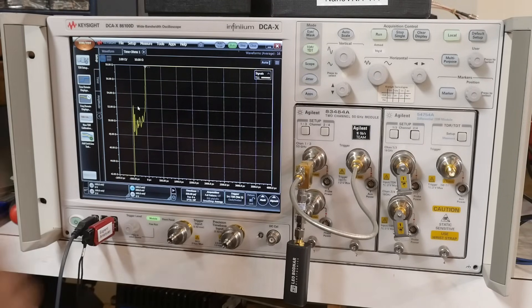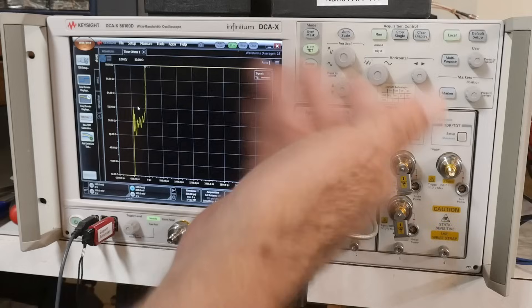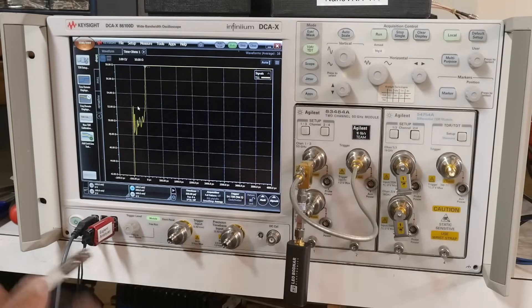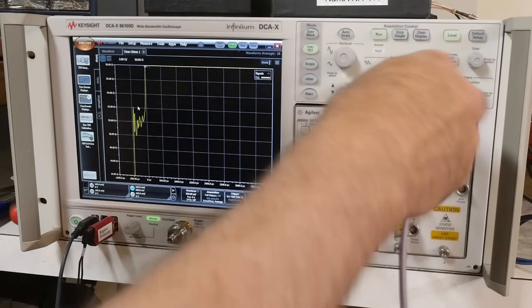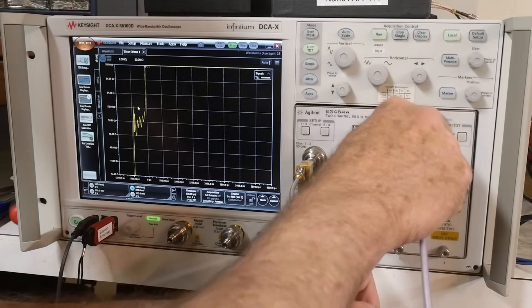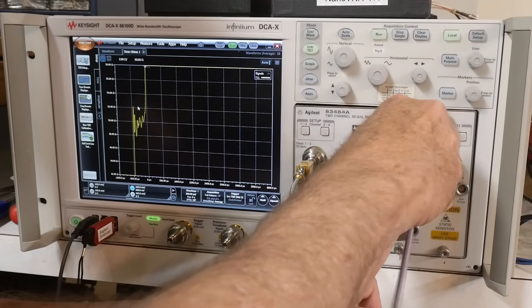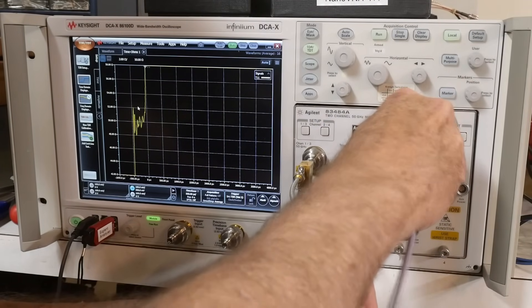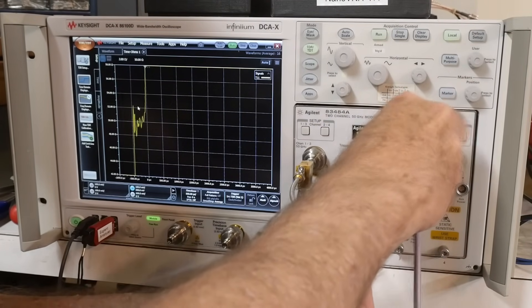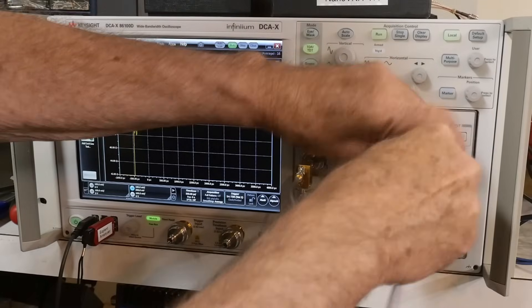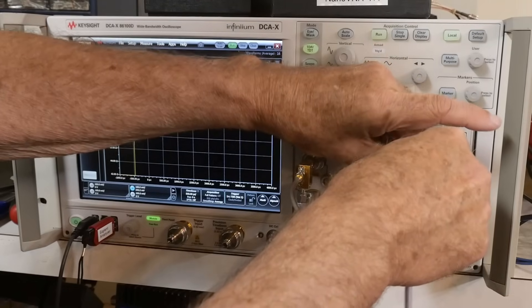This big spike up is the open. The connector right now doesn't have anything attached. So let's go ahead and attach our cable here. And what it's going to do is it's going to launch a pulse down this cable and it will look at the reflected wave.